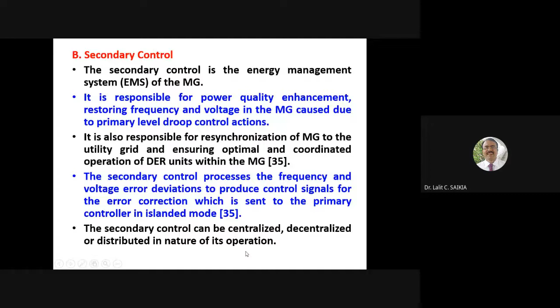Say we want to connect the microgrid into the utility grid - resynchronization needs to be done, and secondary control is responsible for it. Secondary control processes the frequency and voltage error deviation to produce a control signal for error correction, which is sent to the primary controller in islanded mode. Secondary control can be centralized, decentralized, or distributed in nature of its operation.